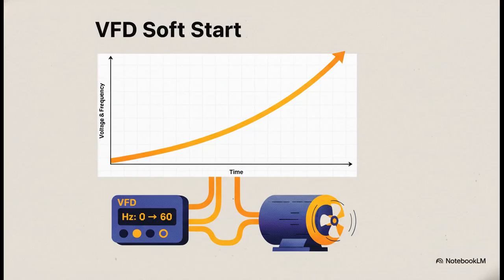So remember that massive 5 to 7 times inrush current we talked about? With a VFD, poof, it's gone. It just disappears. By starting the motor at 0 voltage and 0 frequency, and then gently ramping them both up together, the VFD gives you the smoothest start imaginable, totally eliminating that electrical jolt.